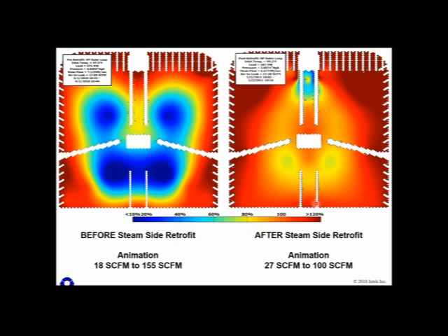And so after the retrofit, we installed a proper air cooler, went through a whole design effort and approvals, and made the design. We're there to oversee the installation of the parts pieces to make sure that we vented out this bundle much more effectively, and you can see the results in the performance profile post retrofit.